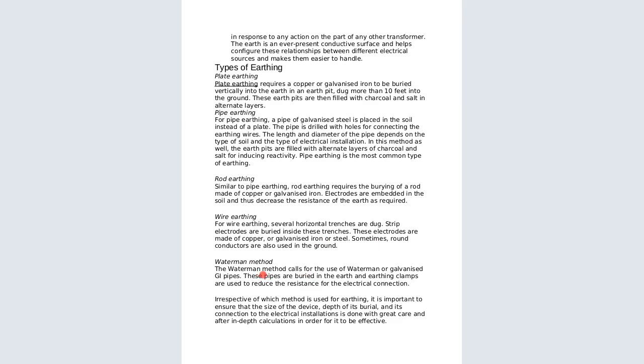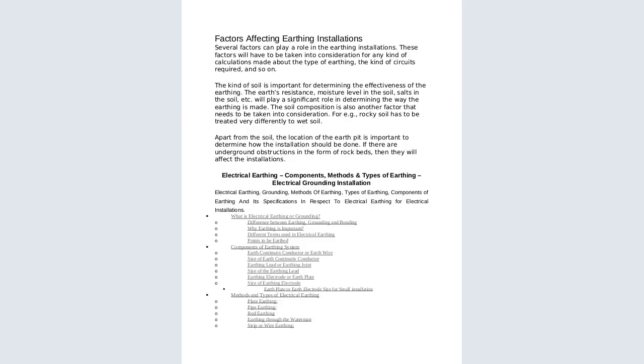Another kind of earthing is the Waterman method. The Waterman method calls for the use of Waterman or galvanized GI pipes. These pipes are buried in the earth, and earthing clamps are used to reduce the resistance of the electrical connection. So irrespective of which method is used for earthing, it is important to ensure that the size of the device, the depth of its burial and its connection to the electrical installation are done with great care and after in-depth calculations in order for it to be effective. As I said, we are going to go through these steps and look at the pictures and diagrams of how the installation is done and the materials that are needed for this earthing.